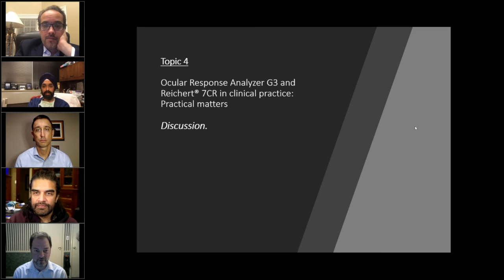This gets into the waveform score issue, which I know the other panelists have opinions on and experience with. My first suggestion would be, whenever the waveform score is low, question the accuracy, make another measurement, make a couple extra measurements. The waveform score is a signal quality from 0 to 10. And I think the recommendation for the manufacturers, once you start getting down below 6, you have to start considering that perhaps the quality may not be as high as you like.